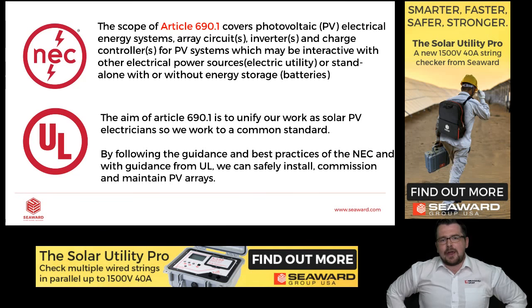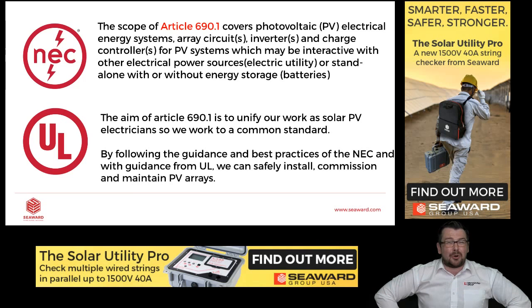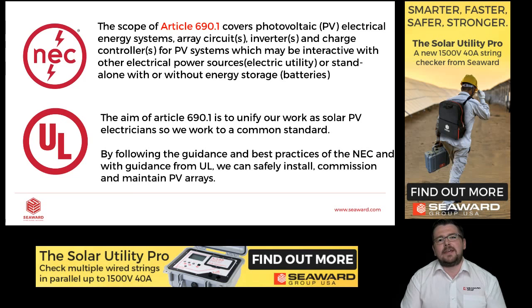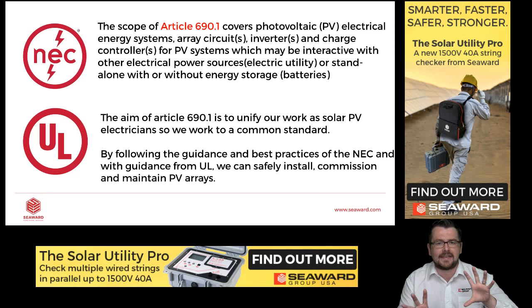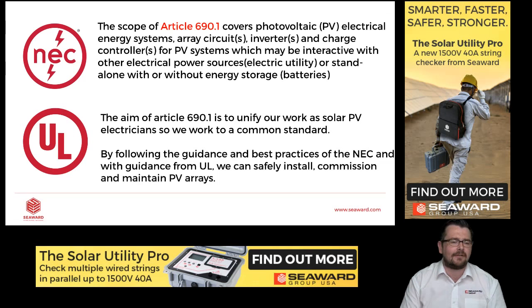Similarly, if you're in North America, we can look at the National Electric Code, Article 690.1. That has a lot of details. It also covers the rapid shutdown requirement for residential systems. It also covers DC optimizers and a lot of other things. It's very good. Not all states have adopted 690.1, but the majority have.